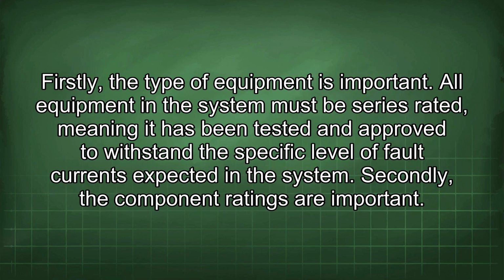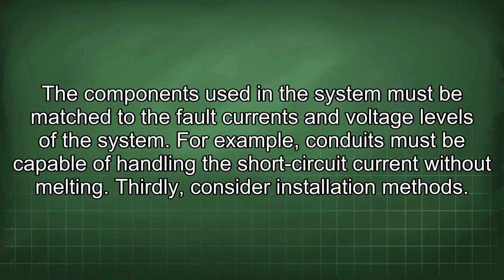Firstly, the type of equipment is important. All equipment in the system must be series-rated, meaning it has been tested and approved to withstand the specific level of fault currents expected in the system. Secondly, the component ratings are important. The components used in the system must be matched to the fault currents and voltage levels of the system. For example, conduits must be capable of handling the short circuit current without melting.